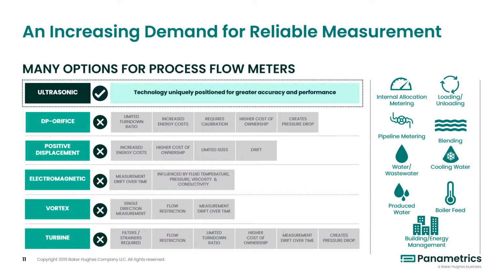Ultrasonic flow meters are being selected more and more due to the increased demand for reliable flow measurements. Ultrasonic flow meters are uniquely positioned for greater accuracy and performance with no maintenance. Users have many options for internal allocation meters, pipeline monitoring, process measurements within their unit operations, blending, and other such applications. However, more and more users are continuing to transition over to ultrasonic flow meters due to the overall turn down range or ratio, no maintenance, no pressure drop, and advanced diagnostics.